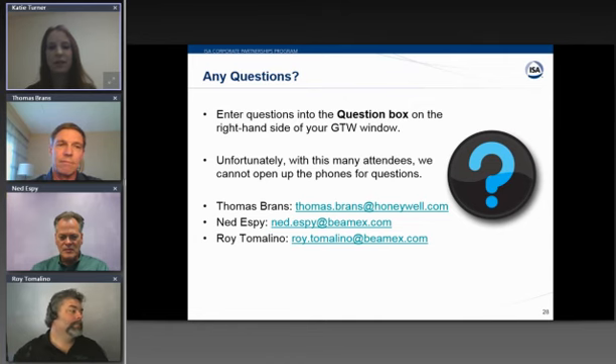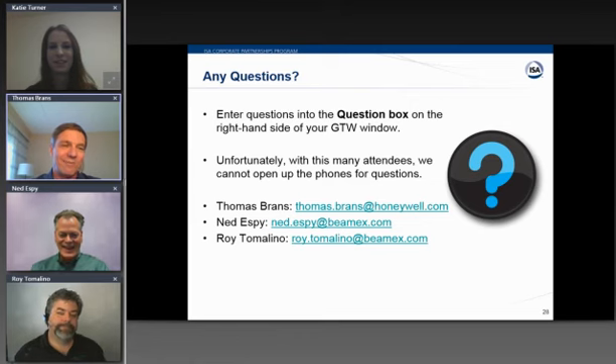Okay, next question is, what is more accurate, an RTD or a thermocouple? It's an RTD. That was covered in part 1. Yeah. So an RTD is typically a 0.1 degree C device, a thermocouple plus or minus 1 degree C. That's just a rule of thumb. Yep.